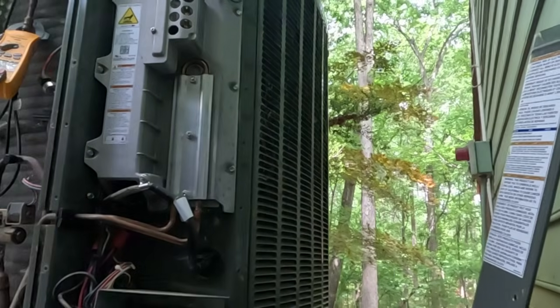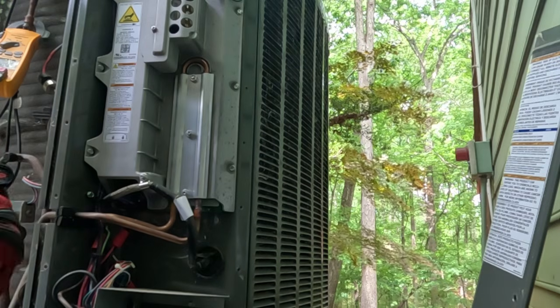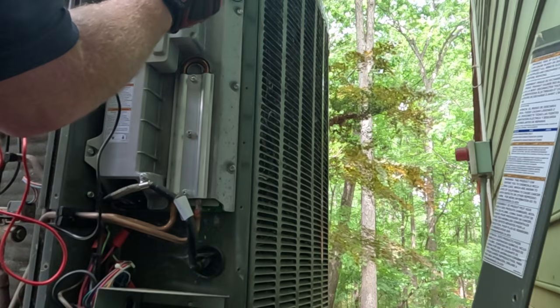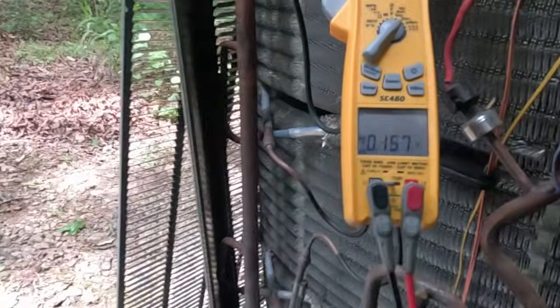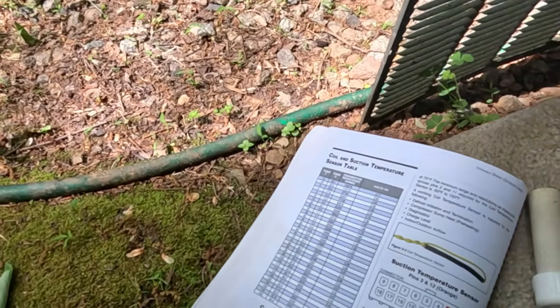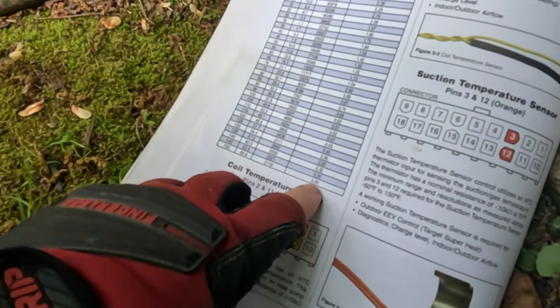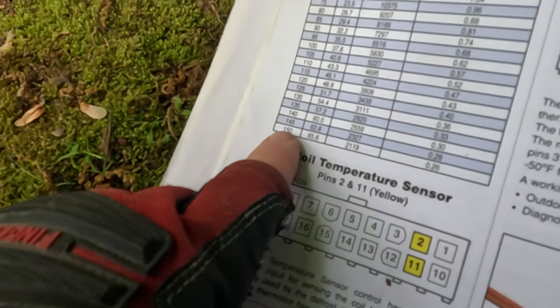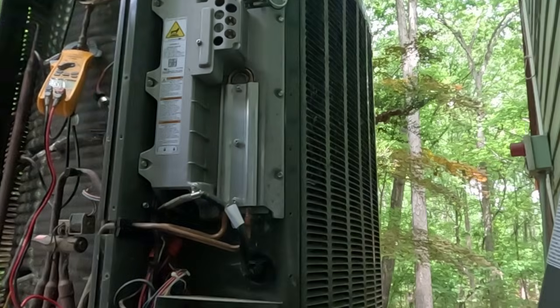So this thing is 245, 46 millivolts. So I'm going to put my range directly to DC voltage and double check that. That's an auto ranging meter, so I don't always trust it to be exactly where I need it. There's certain situations, but anyway, right there, getting 0.2, so it was reading right. I just want to see it in a DC reading because that's what our chart goes by. So 0.2 volts DC. Oh gosh, 0.26 is 150 degrees, and I know it's not 150 degrees out here with this unit not running, and the outdoor temperature is 65, so that's going to be no bueno. Bad sensor. I'm going to get it swapped out real quick.